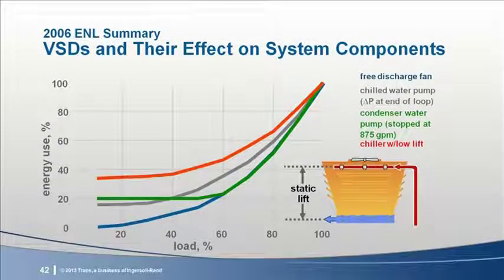In the 2006 ENL, this chart was shown as an example of how the various components in a chilled water system might unload under a specific set of conditions and control sequences. There are two things to take from this chart. First, all the components unload somewhat differently and not to the cube of the speed ideal. And second, if the components of the system were unloaded as shown, it would be an efficiently operating system. Unfortunately, this is seldom the case in most systems, nor is it quite that simple. But with proper control, we can do significantly better than is typical today.